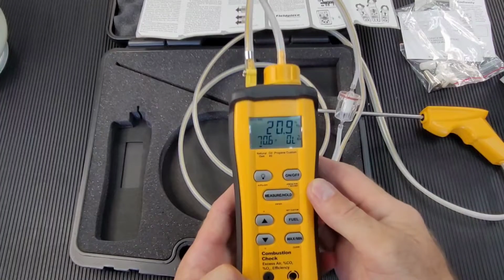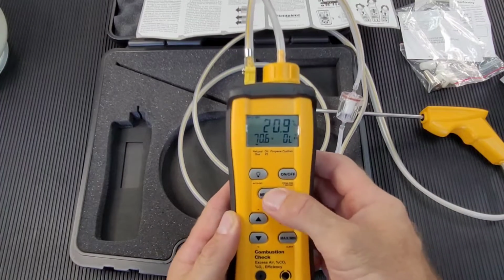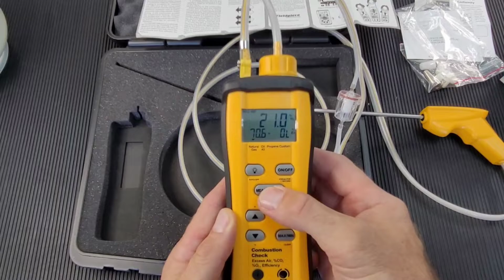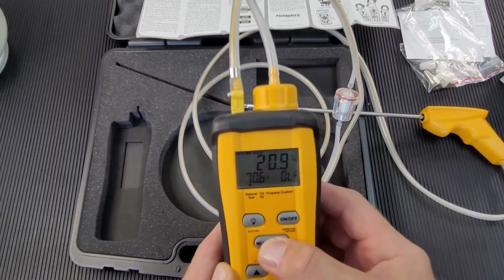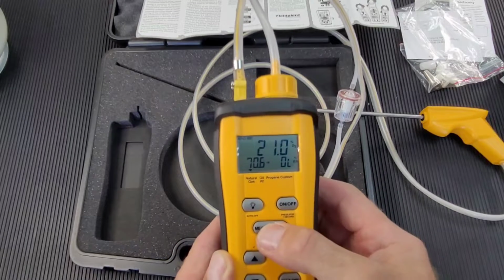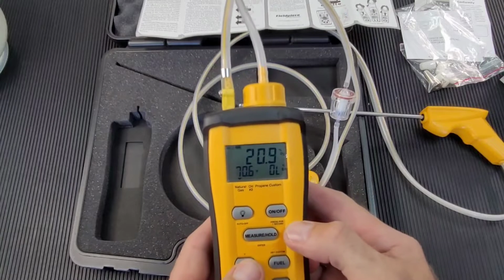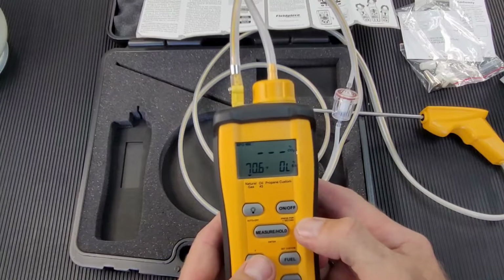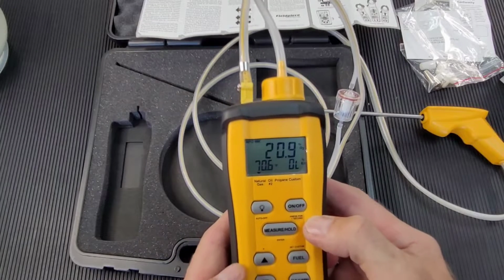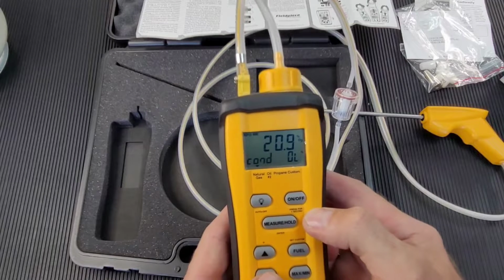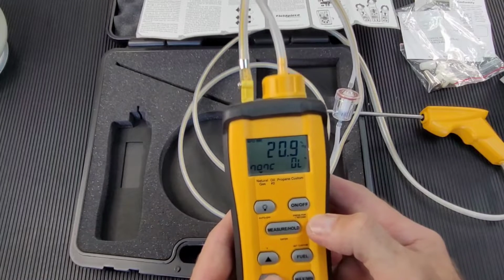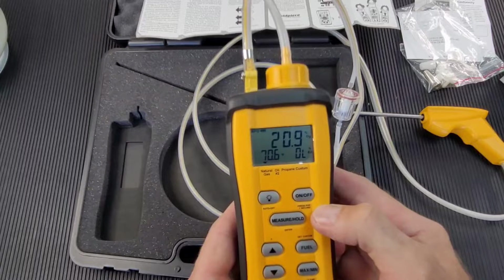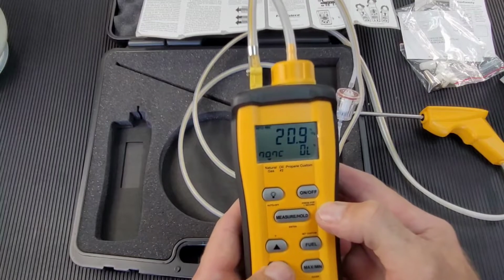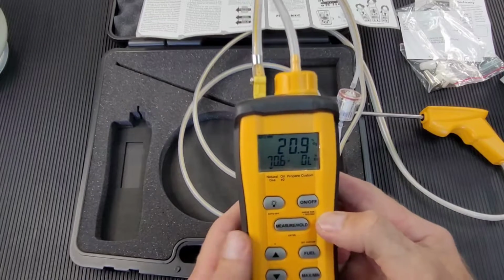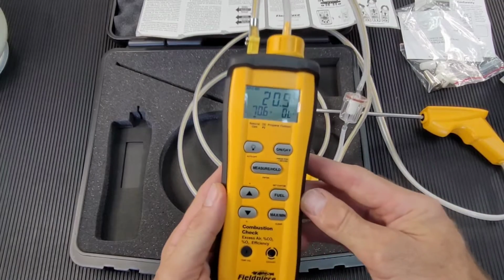Very good, very good. And again, this is your measure, hold, and you could see the little icon says hold. When I press it, it's on normal. Okay, up arrow is CO2 calculation, will not calculate because we're at ambient 20.9. Down arrow is condensate, and none, 70.6. Okay, there is some EA also. Okay, excess air.